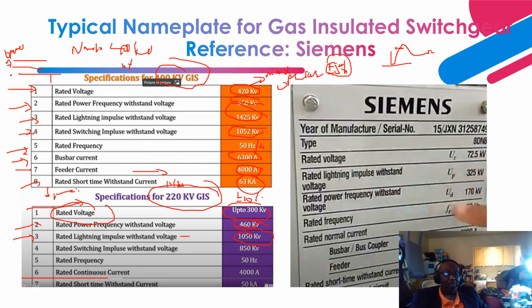And this is the amount of overvoltage that it can withstand due to a lightning strike. Next is the switching impulse due to operation of a circuit breaker, open and close, and the rated frequency, either 50 Hz or 60 Hz. Rated continuous current, that is for the bus and also for the line side, the feeder. This is how much capability it's rated for, and also the short time withstand current, that is 1 second or 3 seconds, 50 kA.